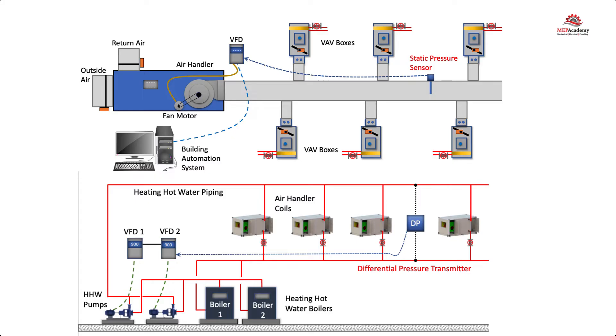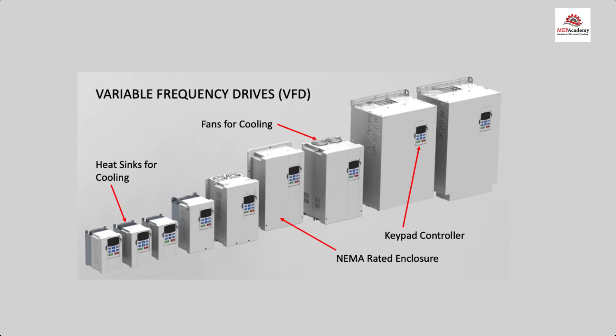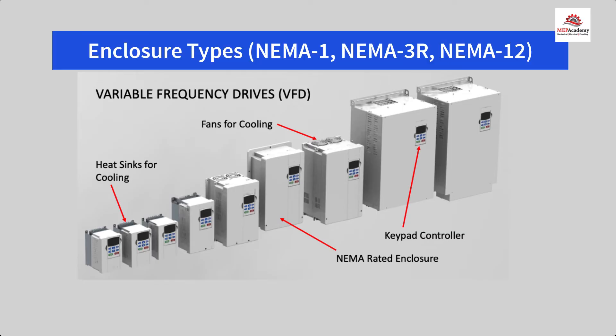You'll also need to select an enclosure type — whether it's inside, outside, or exposed to elements. VFDs are usually located in mechanical rooms or outside near the equipment. Depending on the type of environment that surrounds the VFD, there are various solutions for the enclosure type as indicated by the NEMA number. The most common in the mechanical industry are NEMA 1, 3R, and 12.